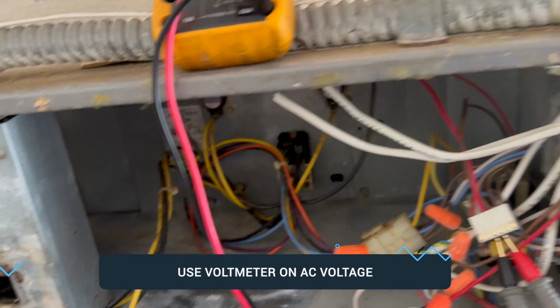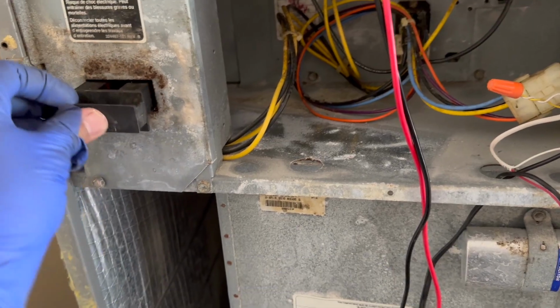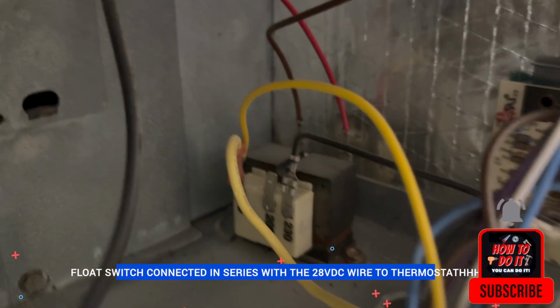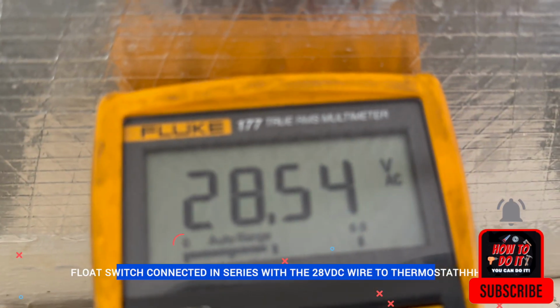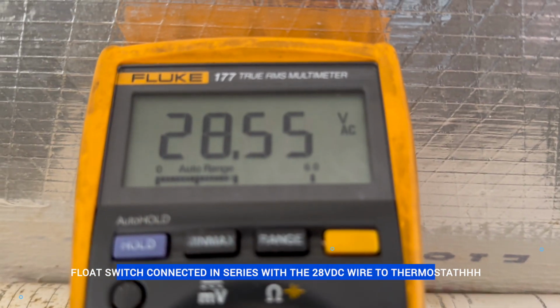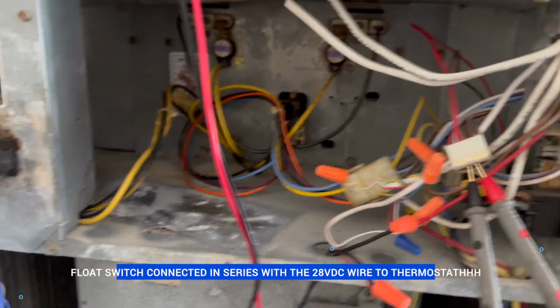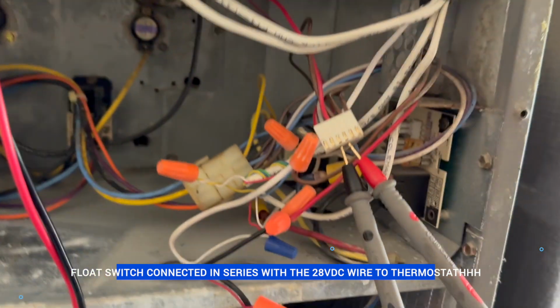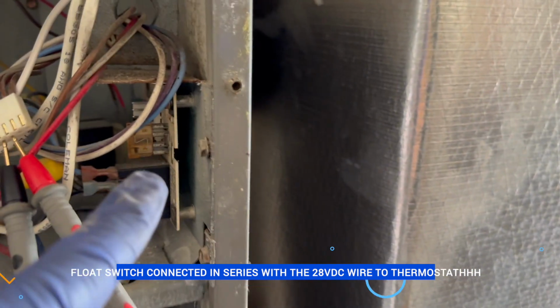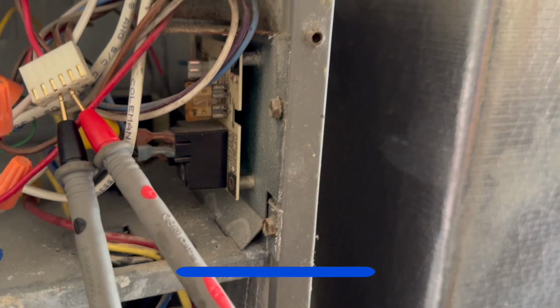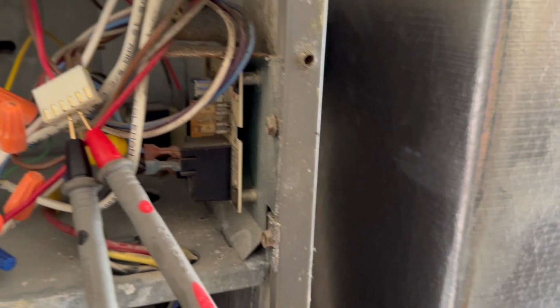Since everything looks good, I'll go ahead and plug it in. And there you go, 28.5. That tells me my transformer is good. Remember this is AC voltage, not DC, so make sure you're checking on AC. So that tells me I do have power here, my transformer is working. It could be something with this board that isn't transferring power back to there.